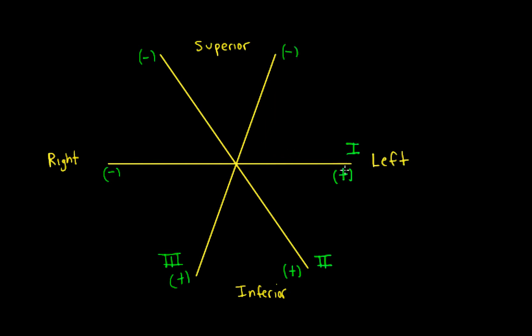Now let's add the unipolar leads — the augmented voltage leads. These are called unipolar because they're not subtracting one electrode from another; instead, they record the electrical voltage at one electrode relative to a zero potential. That zero potential is obtained in the electrocardiograph machine by joining the three extremity leads to a central terminal, where the sum of the right arm, left arm, and left leg electrodes equals zero, giving the central terminal a zero voltage.